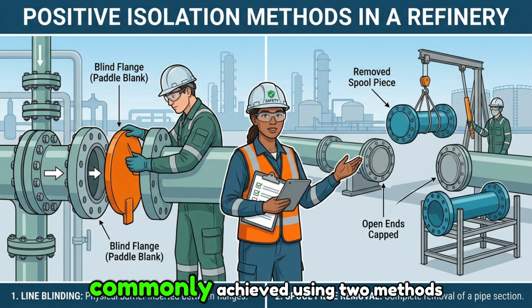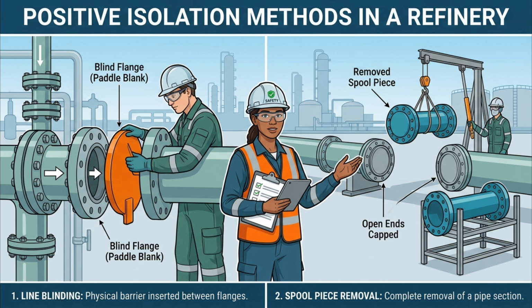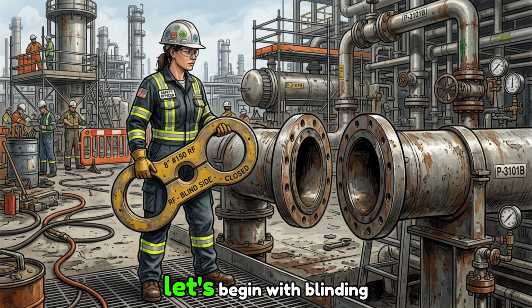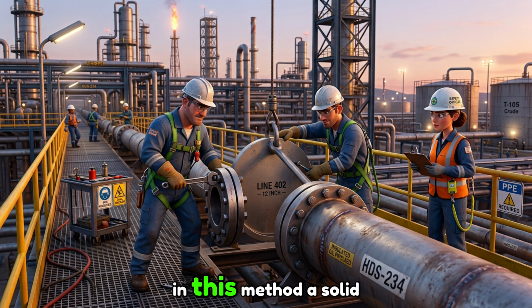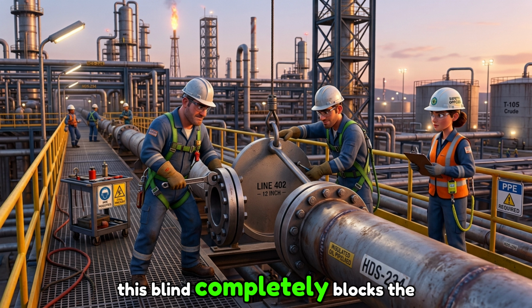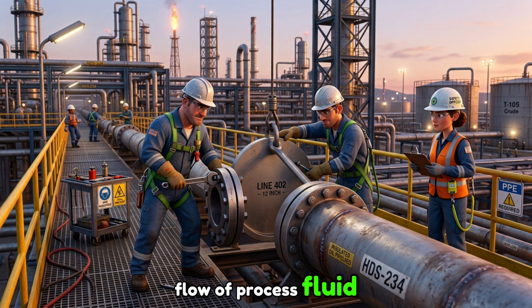Positive isolation is commonly achieved using two methods. The first method is blinding. The second method is spool removal or pipe disconnection. Let's begin with blinding. In this method, a solid metal blind is installed between two pipeline flanges. This blind completely blocks the flow of process fluid.